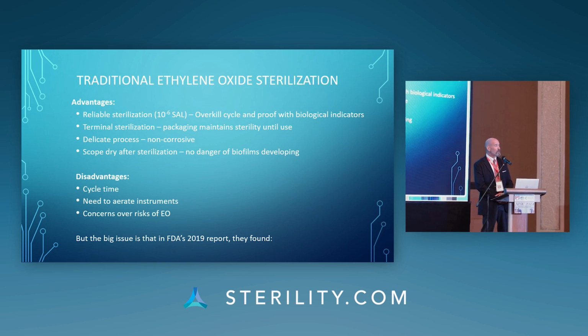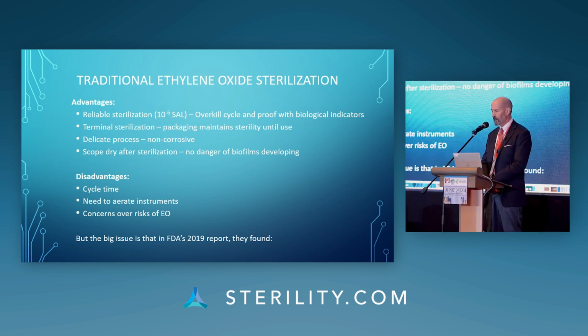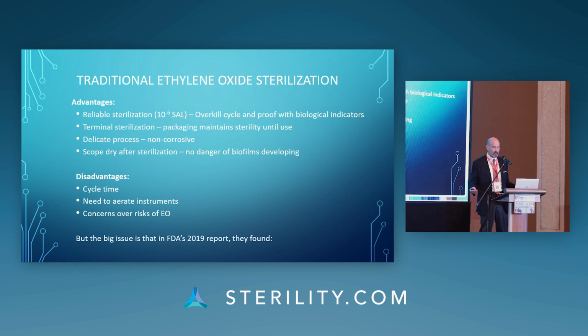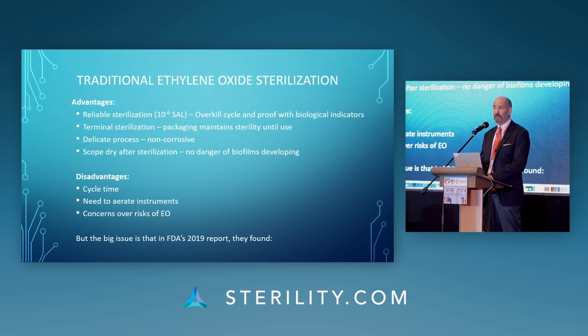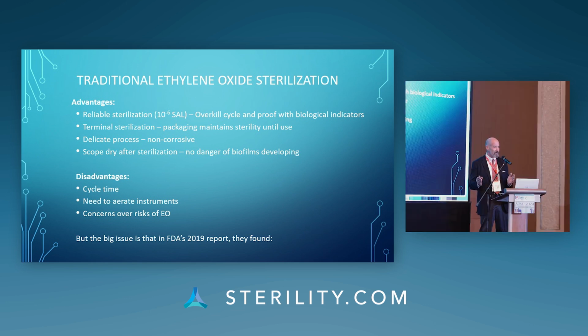Ethylene oxide is non-corrosive, and so it will not damage scopes, it will not damage other instruments that you're processing. And very significantly, at the end of an ethylene oxide process, you're left with a scope that is completely dry. There is no potential for the growth of biofilms. And a number of researchers in the United States have said this may be the most important thing about ethylene oxide sterilization, the fact that you end up with a bone-dry scope.